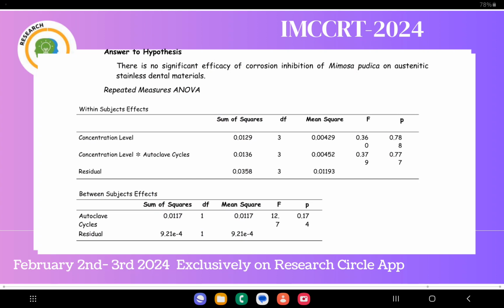For concentration level, the F statistic was 0.360 with a p-value of 0.788, suggesting no significant impact on corrosion inhibition. Similarly, the interaction effect of concentration level and autoclave cycles yielded an F statistic of 0.379 with a p-value of 0.777, indicating no significant combined influence. The residual within subject effects, representing unexplained variance, were relatively small.